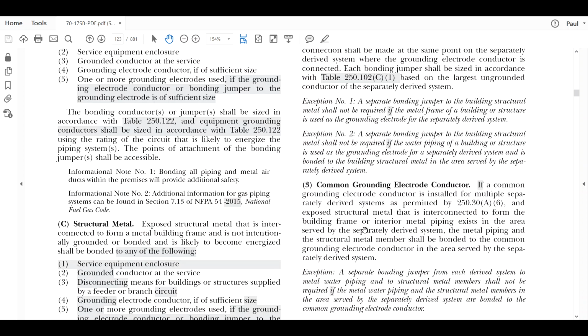Now there's a third option. The third option says, what if I have a common grounding electrode conductor? That's a conductor that runs from, say, the first floor all the way up a chase to the 10th floor, and that's called a common grounding electrode conductor. If that's the case, then I can make the connection over to it. It's just a convenient way to do it, and you are permitted to do it that way under 250.30(A)(6). If the exposed structural metal that is interconnected to form the building frame or interior metal water piping exists in the area served by that separately derived system, kind of regurgitating what we already know, the metal piping and the structural metal members shall be bonded to the common grounding electrode conductor in the area served by the separately derived system.